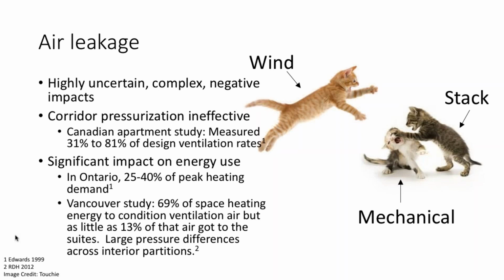Studies show how we ventilate these older buildings using corridor pressurization. You have an air handling unit on the roof drawing in fresh air, conditioning it, and pushing it into the common corridors. Ideally it creates a positively pressurized space that prevents cross-contamination between suites when doors open, because air should rush in underneath those door undercuts. But because the effects of wind and stack quickly overwhelm the mechanical pressures created by those air handling units, we know these systems don't work very well now.